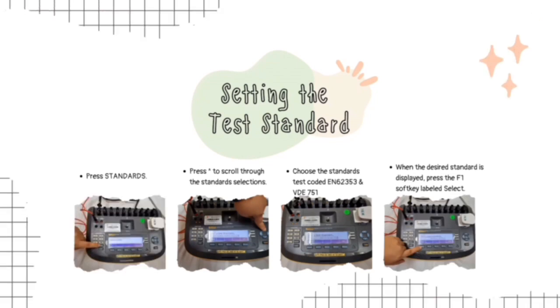First of all, we must set the test standard. First, we must press the standards button on the analyzer. Then, to scroll through the standard selection, press the below button as shown in the figure. Choose the standard test code EN62353 and VDE751. When the desired standard is displayed, press the F1 soft key labeled Select.